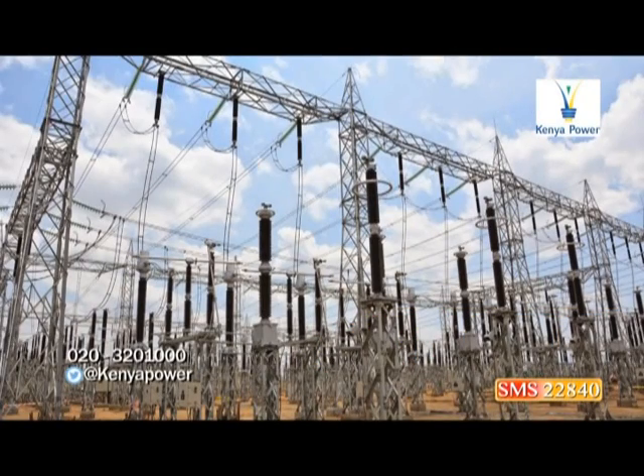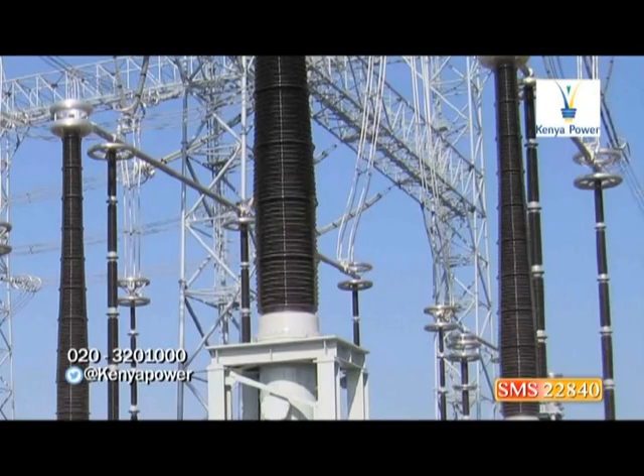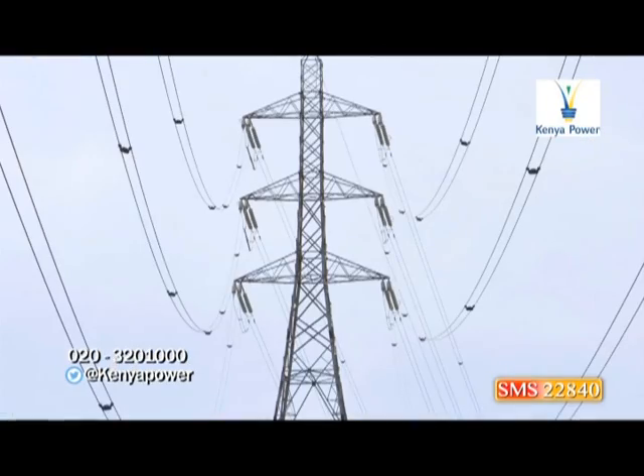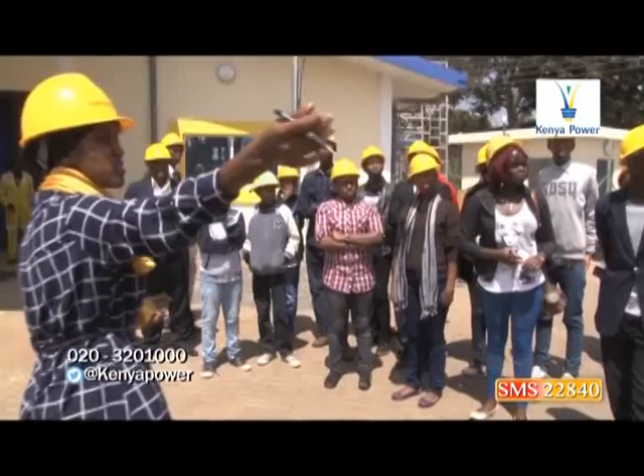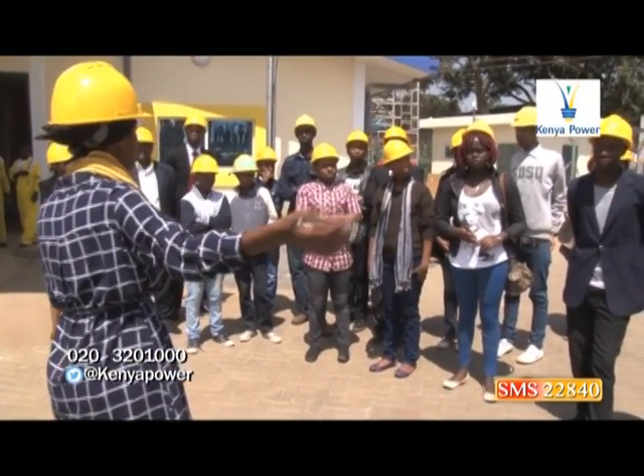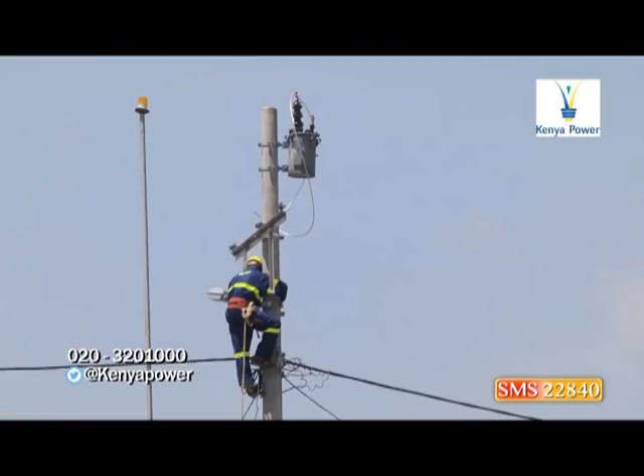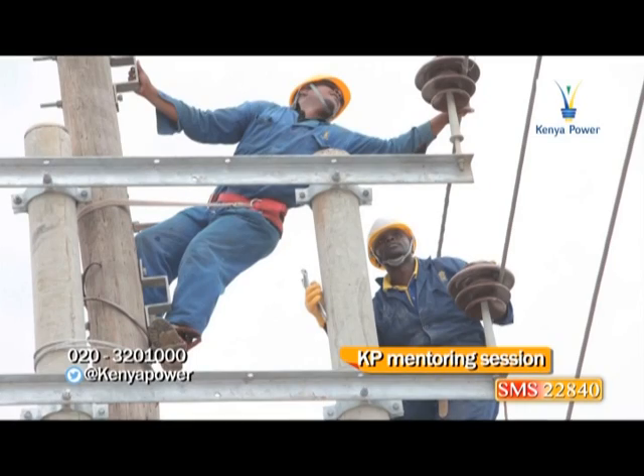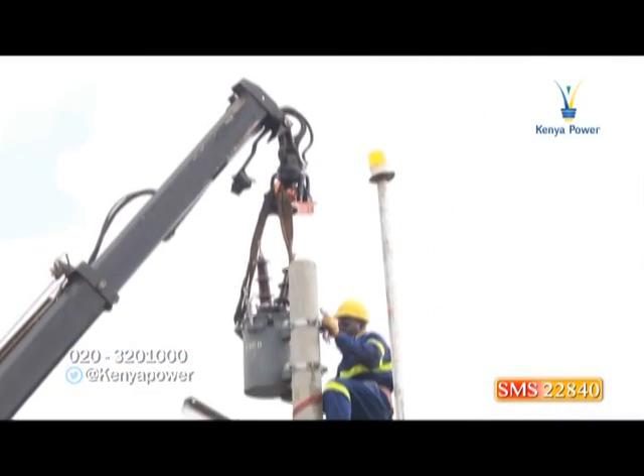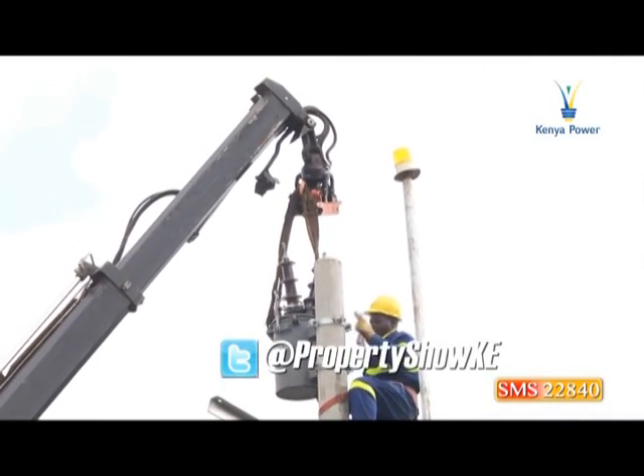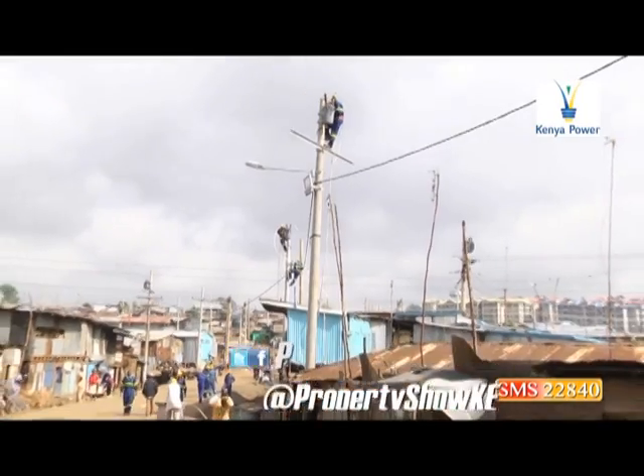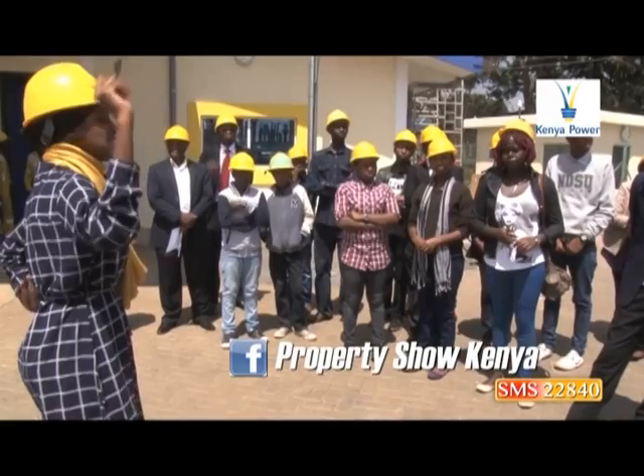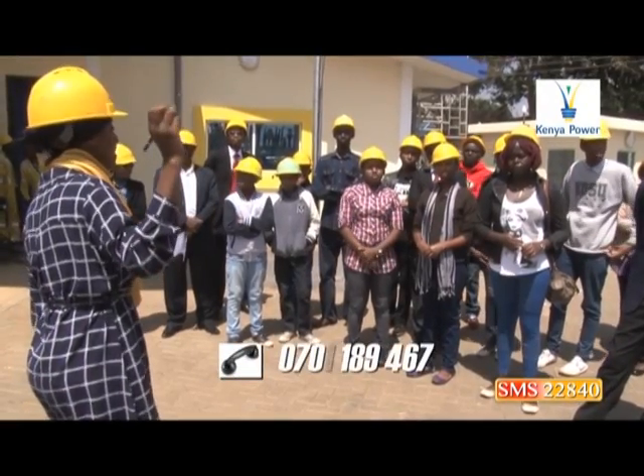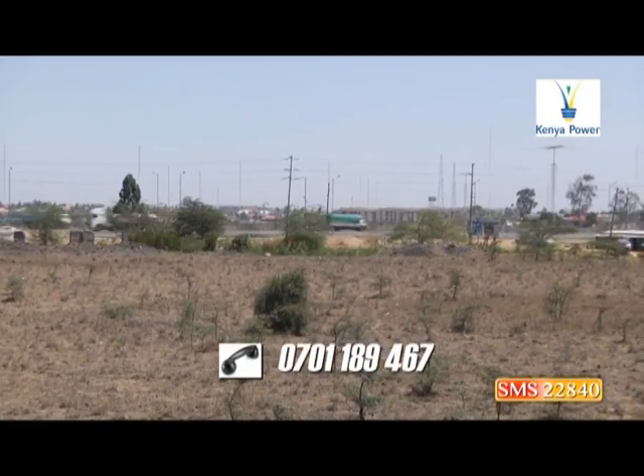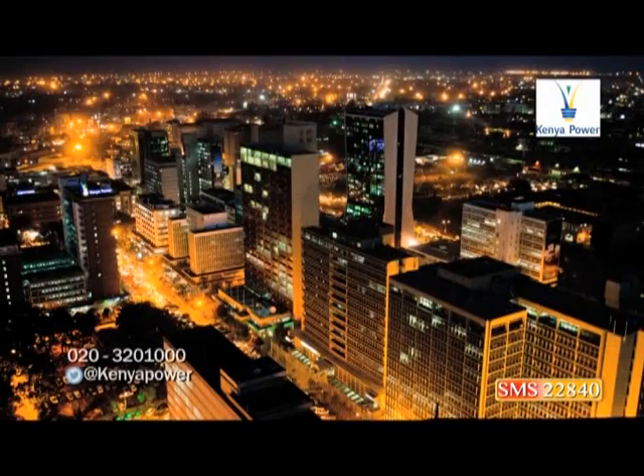This is the outdoor substation where we have a transmission line coming in. The transmission voltages are usually 220, 132, and in Nairobi we have 66 kV, which is used as a sub-transmission because some customers are supplied at 66 kV. But in this particular station, which is a secondary substation, we have the 66 kV voltage stepped down to 11 kV, which is used for distribution around Nairobi.